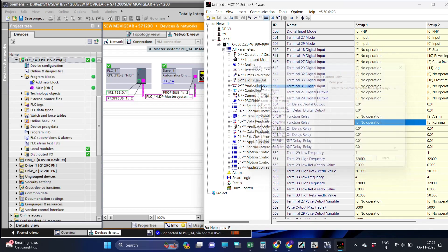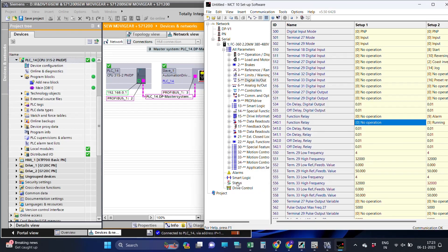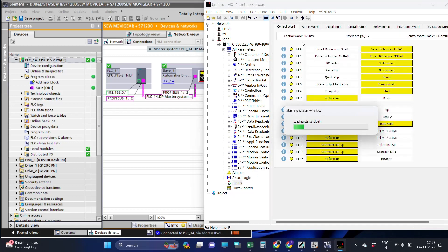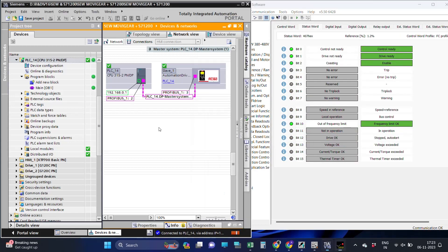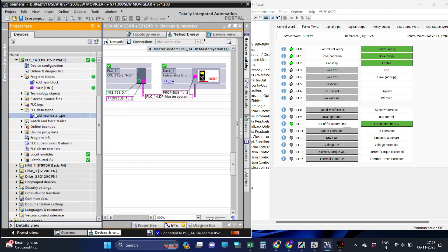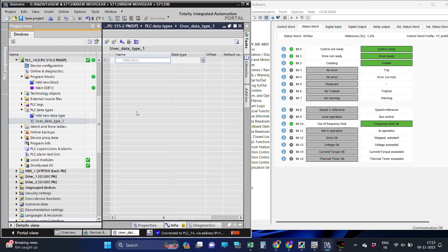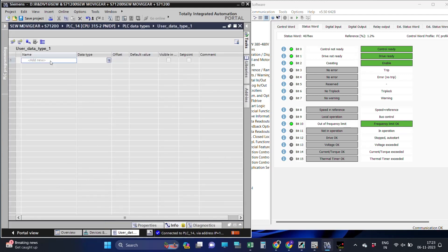As we can see drive status in the MCT software, we will define the status word as well as control word structure in the PLC program. Keep in mind, start defining status and control word bits from the bit address 8 to 16 first, and then bit 0 to 7.